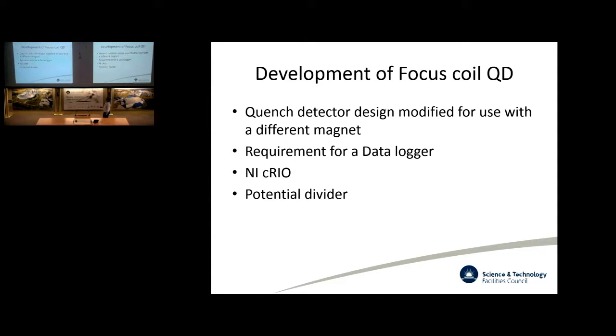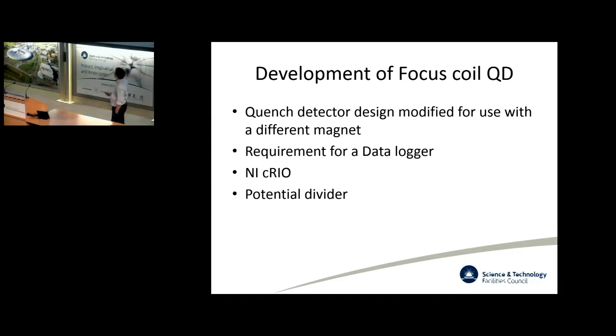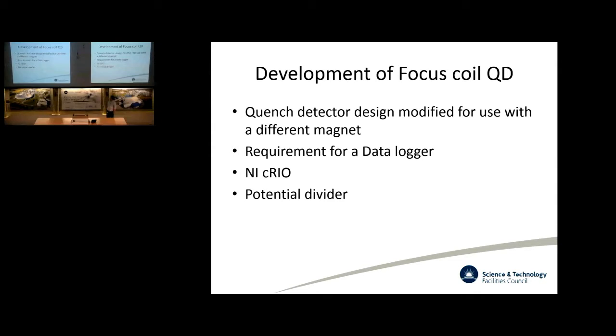So once we'd finished with the decay solenoid, we then implemented this system on the focus coil, another magnet in the cooling channel. Again, it worked very well. However, this highlighted a requirement for a data logger. We utilised a National Instruments CompactRIO data logger, which worked really well. It's got 0 to 10 volts input, but it can actually take up to 60 volts going into it. However, this wasn't quite enough for putting it on a magnet that can come up to maybe 600 volts. So what we did was we installed a potential divider to keep the voltages down.